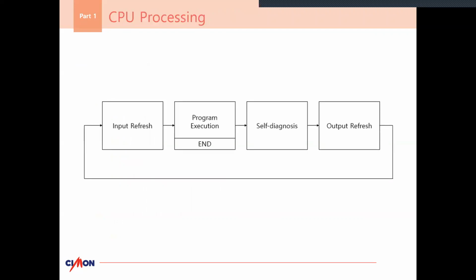A little bit about our CPU processing: when you first initiate the program, it will do an input refresh, checking all of its inputs to see if they're on or off. It will execute the outputs, then end the program. After that, it commits a self-diagnosis, making sure nothing's wrong, because if something is wrong, someone could be damaged or hurt. We don't want to commit an operation that will cause an error, so someone potentially wouldn't be hurt. Then we have an output refresh that resets the whole output since it's already been committed to in the program execution, and we rinse and repeat this whole cycle over and over again.